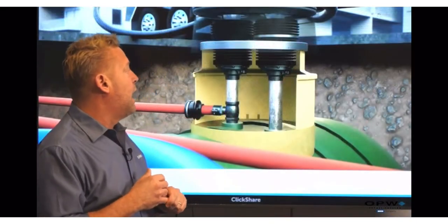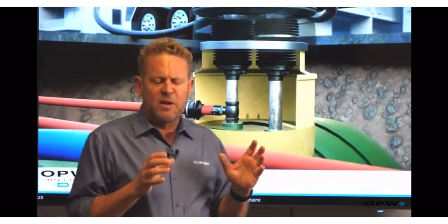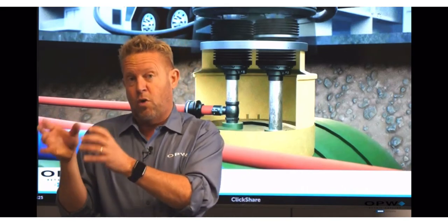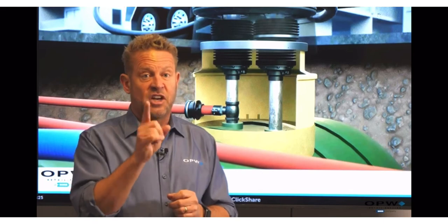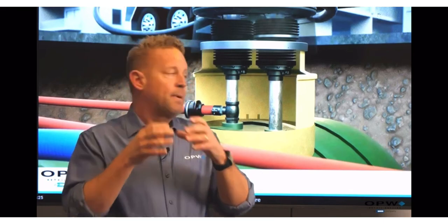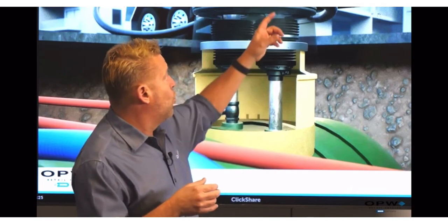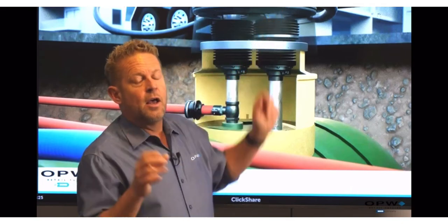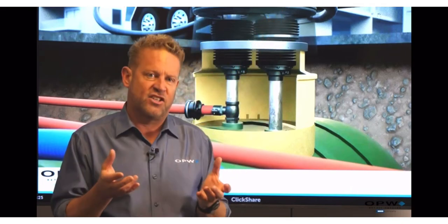In some cases, especially in older tanks, when we started going over to or requiring stage one vapor recovery, they may not have had enough openings on their tank to have a two-point, so they will use what's called a single-point fill. The way that works is there's one riser pipe and one hose, but the hose is actually what we call coaxial, coaxial meaning kind of a hose within a hose.